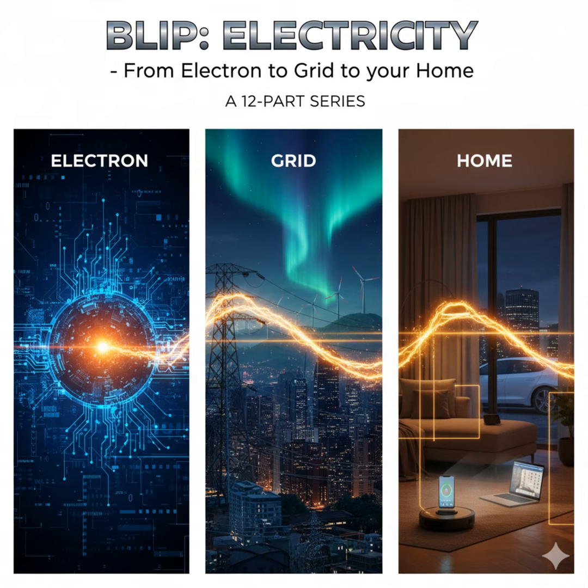And managing it properly, generating it locally, using capacitor banks for steady loads, deploying advanced tools like StatComs for dynamic stability, is crucial. It's vital. It minimizes that excess current draw, which means less energy wasted as heat, allows for smaller and less expensive wires and equipment, avoids those costly utility penalties, and keeps the grid stable. It really touches everything from the physics of electromagnetism right down to your electricity bill, potentially.